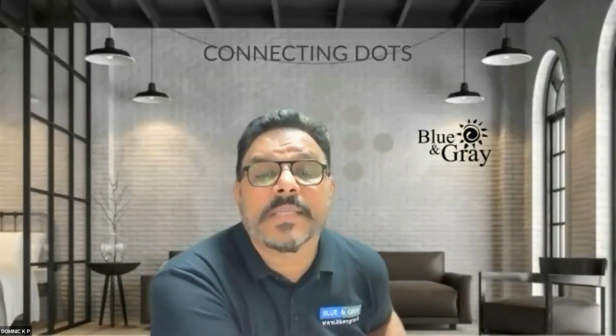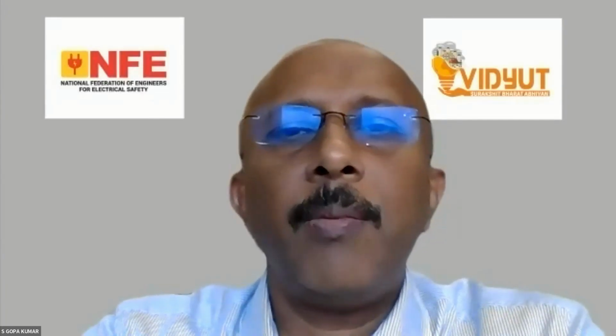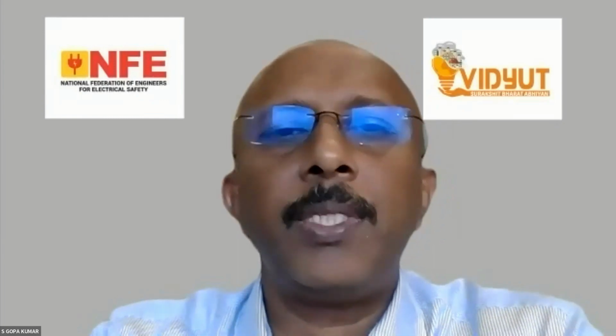Jatin Panchal is asking, as per NEC 2023, can you please highlight the use of fire survival cable for wiring the fire emergency in hospitals? Does it talk about fire survival cable in NEC? Yes, fire survival cable is required for the emergency supply, not emergency, we call it safety service. Okay, so for the fire safety service, yes. But please note that it is not only the fire survival cable, the entire electrical installation must withstand a certain time. That means the clip, clamp, conduit, supports, fixings, lights, junction boxes, and so on.